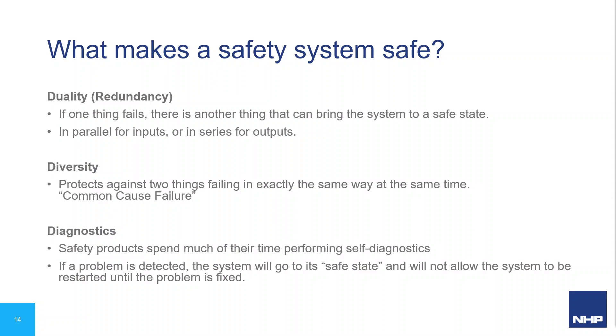What about a safety control system makes it safer than any other control system? Three Ds: Duality, Diversity, and Diagnostics. Duality, or redundancy, ensures failover in our system so that if a fault occurs somewhere in the safety control system, it can still operate effectively and bring the machine to a safe state — typically realized as multiple devices operating in parallel or in series.